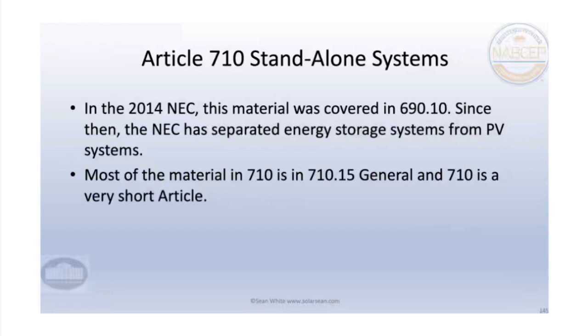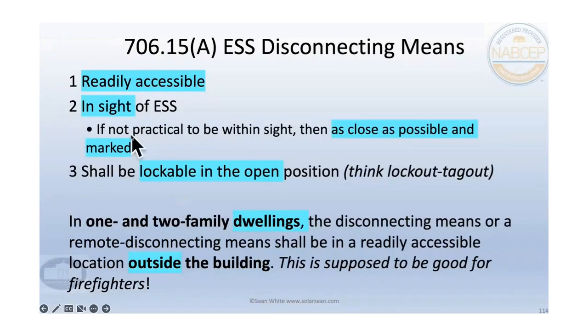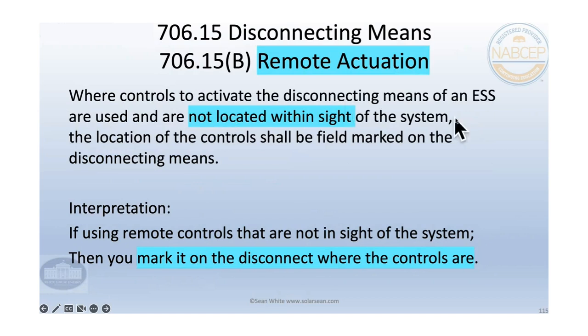So is an emergency shutdown switch required to shut down everything? And can it be microprocessor controlled or mechanical? Yeah, either way. Yep. Let me see if I could see where we were just talking about that. Okay, so let's see. So disconnecting means readily accessible in sight. This is kind of funny too. It says in sight, but if not practical, as close as possible, shall be lockable in the open position, 1 and 2 family dwellings outside of the building, and where controls to activate are used and not located within sight of the system, like outside that we were talking about, location shall be field marked on the disconnecting means.